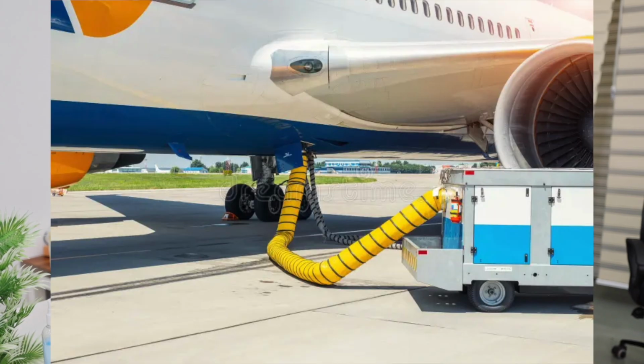After that, that air handling unit supplies the air to the Glycol. Then there is a primary coil. That is a normal coil. The primary coil decreases the air temperature to around 6 to 8 degrees Celsius, mostly 6. And after that, that particular air will pass through the glycol coil. Then the temperature will come down to 0 degrees Celsius. And this temperature is going to the aircraft because that much chill is required to cool down the aircraft very fast. Because the aircraft ventilations are very small, and the CFM is very small. In that situation, very cold air is required. The design is like that for the aircraft.